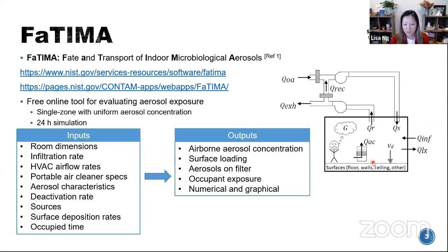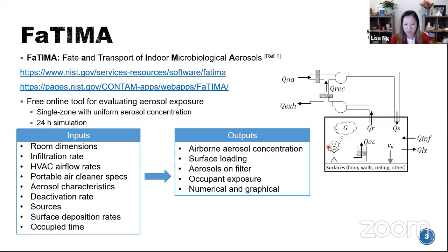You can also input aerosol characteristics such as size and density. A deactivation rate is available — for example if using UVGI or natural decay. A source can be specified — it can be continuous like breathing or talking, or burst such as a cough or sneeze. Surface deposition can be defined for floor, wall, ceiling, and other surfaces: if you had a room full of desks you could have more surface deposition, otherwise you could leave that value at zero. Finally, the occupied time: the source can be generated on a schedule, and the occupied time can be put on a different schedule — both are constant or intermittent within the 24-hour period.